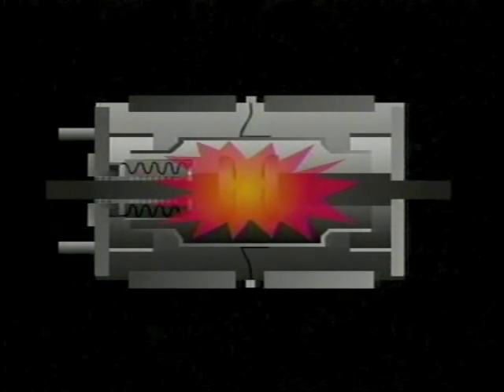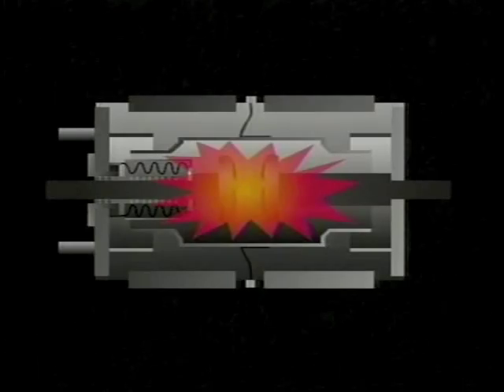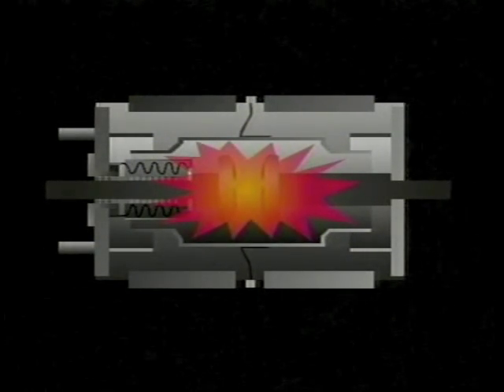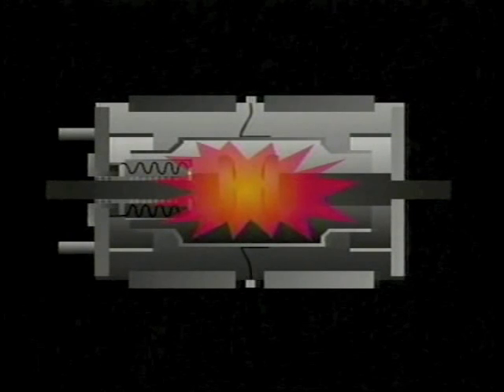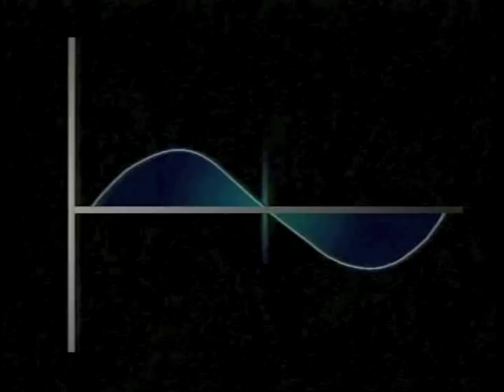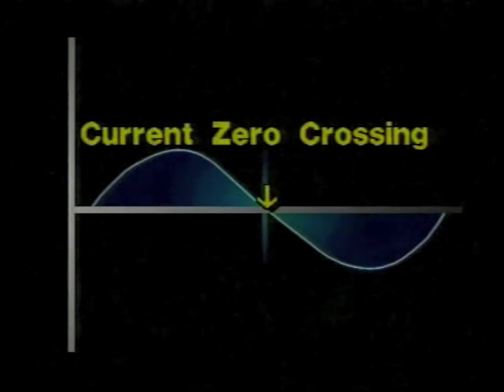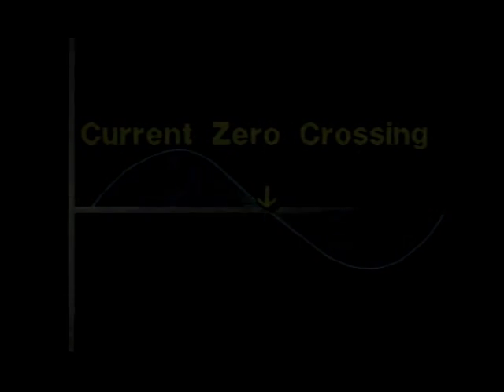This rapid movement limits the amount of electrode erosion and prevents the formation of hot spots on the surface of the electrode. The arc burns in an ionized metal vapor, which continually leaves the contact area and condenses on the surrounding metal shield. At an early current zero, the arc is extinguished and vapor production stops.